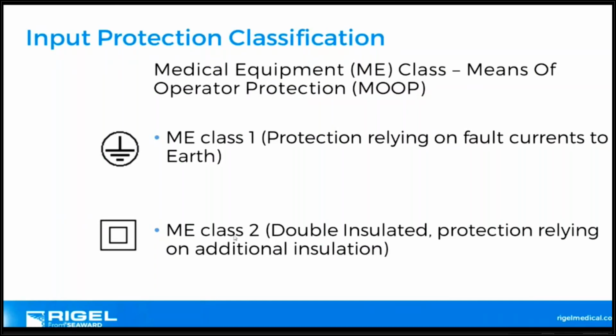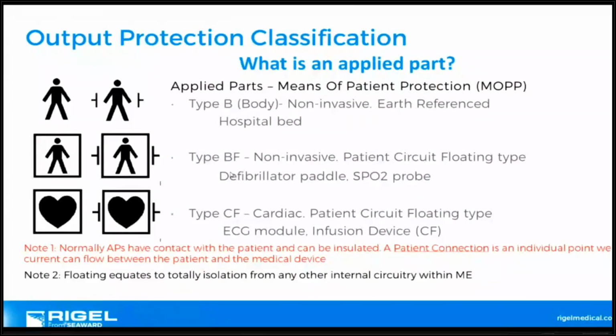With class 2 equipment, we have this box. So these are the two symbols. The square within the square is class 2, and class 2 items can still have exposed metalwork, but they'll have this double isolation barrier, and they'll have proof within the design records that the medical equipment is safe because of this double insulation barrier. So first of all, when you're doing electrical safety testing, you need to clarify: is it a class 1 or a class 2 device? For output protection, we have, basically, this is the applied part. What is an applied part? The applied part is the part that is physically in contact with the patient. Can be insulated.